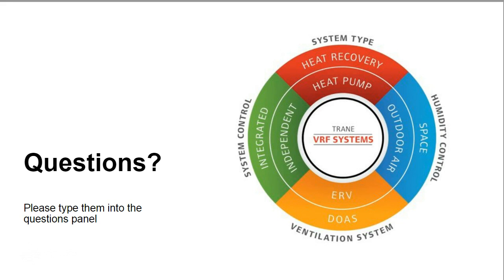I highly recommend that the branch controllers be placed indoors. The reason being that some branch controllers, if not all, are not rated for outside applications. I have seen in some instances where manufacturers can fabricate what we kind of refer to as doghouses for the branch controllers outside. Even though there aren't any moving parts, heat will be given off from these units, so it is important that some sort of DC fan be used to provide cooling for those units. But if there is space inside a building, I highly recommend that be your first method of installation.